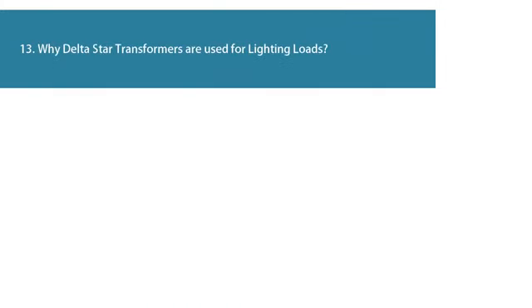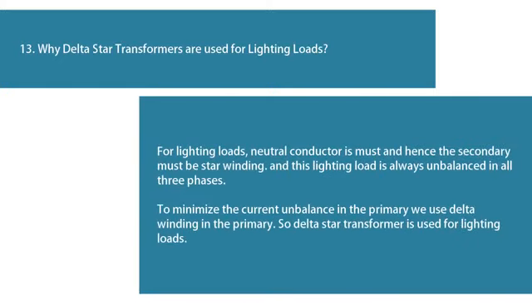Question 13: Why are delta-star transformers used for lighting loads? For lighting loads, a neutral conductor is necessary and hence the secondary must be star winding. Lighting loads are always unbalanced across all three phases. To minimize the current unbalance in the primary, we use delta winding in the primary. So delta-star transformers are used for lighting loads.